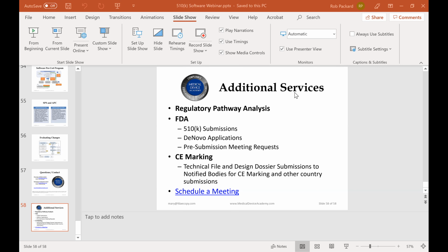So if that's your only question, here's our rationale for 510K versus letter to file. From the day you submit it, they have 60 to 75 days to schedule a meeting or respond by email. And which method they respond by is your choice in your request. But that should answer in terms of timeline. That's how long it takes. We typically request the 60th day, the 61st day, and the 62nd day, and we get what we want less than half the time, but they're usually pretty close. Usually, it's the day of the week and the time of day that they change.